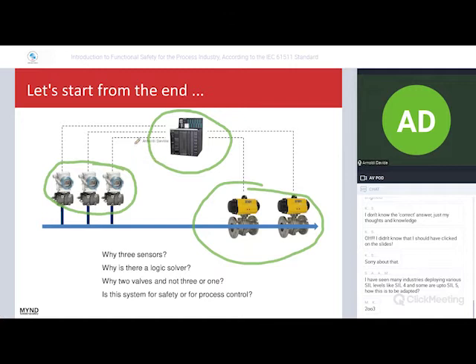I can tell you that three pressure transmitters are lower in reliability than two, but three transmitters are more available than two. But that's a consideration we have to make only with some methodology, not only by experience. Functional safety can help you drive the safety instrumented system in a correct design way.